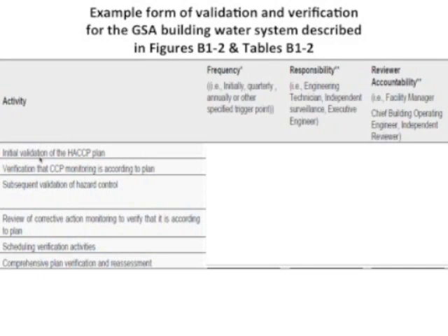say, for example, if the result is above 100 CFU per liter or milliliter, we're going to disinfect the system, but if the result is 85 CFU per whatever unit volume you're looking at, we don't need to disinfect. See, scientifically, that is indefensible because the precision in the data is nowhere near good enough, or it's not adequate for making distinctions like that. So these are some of the reasons why validation evidence is treated in the way it is here. Legionella testing is important when used properly, but it is not to be relied upon. And we understand that that does go quite a bit differently than what we see around the world in some of the other regulations.